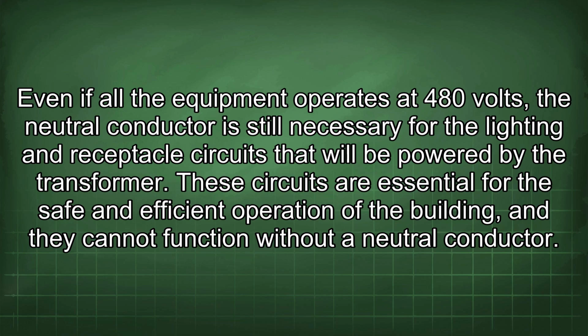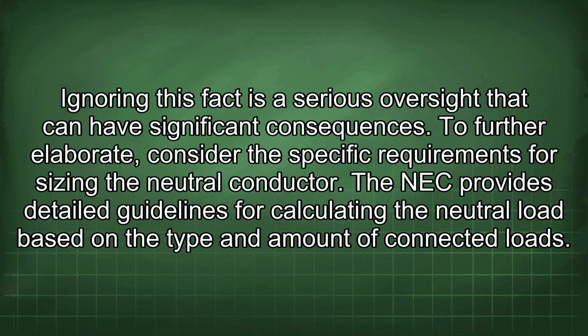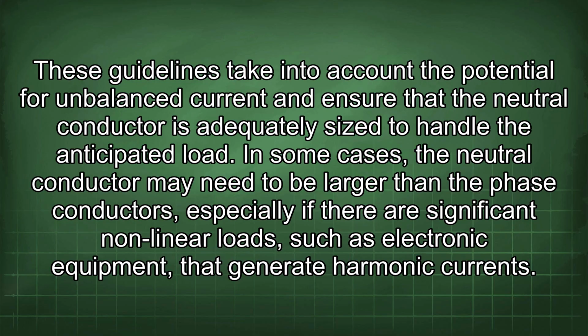These circuits are essential for the safe and efficient operation of the building, and they cannot function without a neutral conductor. Ignoring this fact is a serious oversight that can have significant consequences. To further elaborate, consider the specific requirements for sizing the neutral conductor. The NEC provides detailed guidelines for calculating the neutral load based on the type and amount of connected loads.